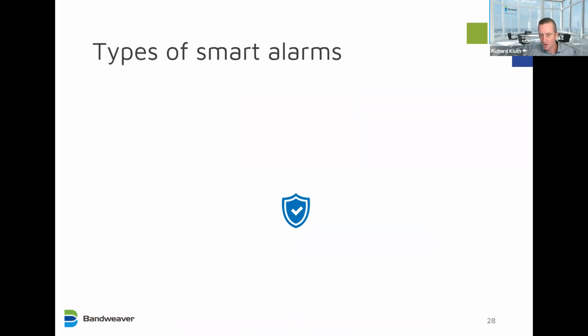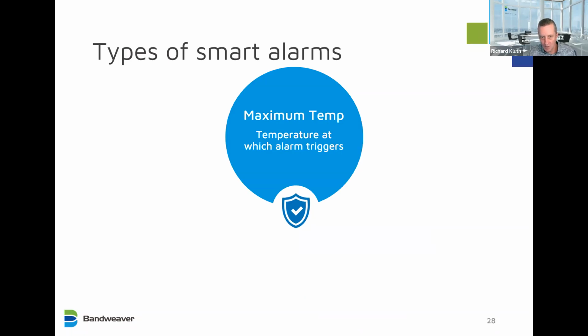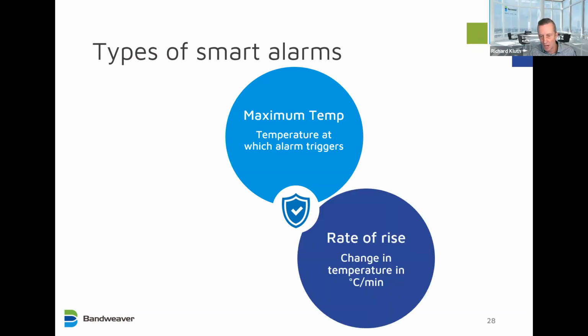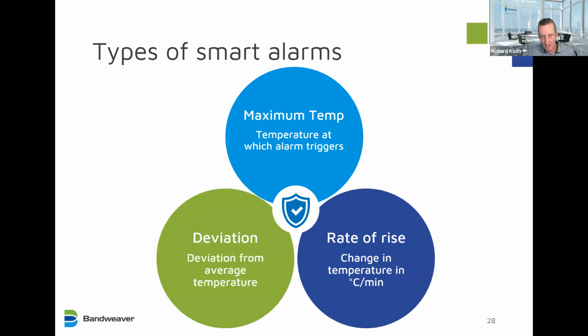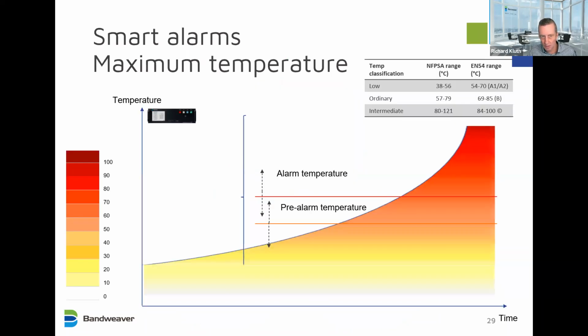So what are the smart alarms? Maximum temperature is similar to conventional alarm setting, except you can configure it to whatever level you want. Then the rate of rise, which gives you the change in temperature in degrees C per minute, and deviation. We'll talk through each of these smart alarms in more detail. For maximum temperature, the alarm and pre-alarm can be defined at whatever level the user chooses. So you have an alarm and a pre-alarm level, and as I said, you can set this wherever you want.